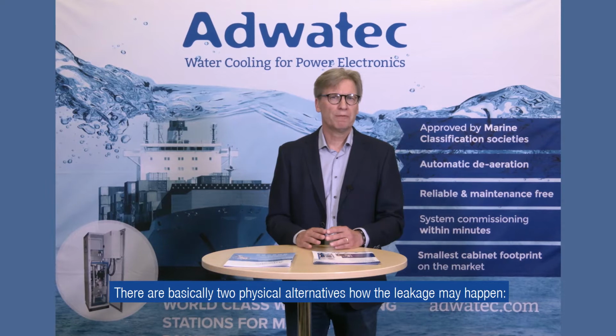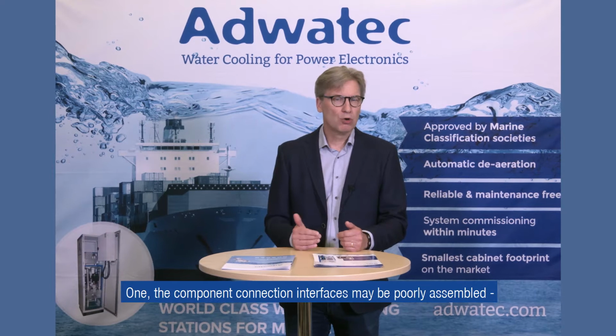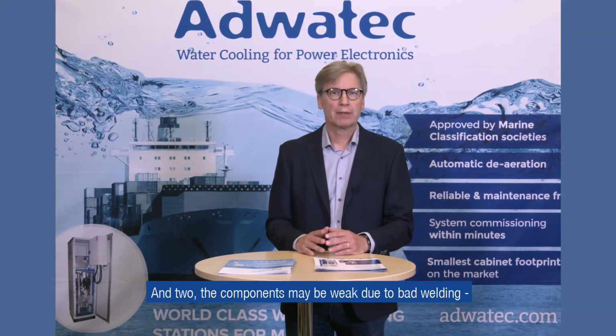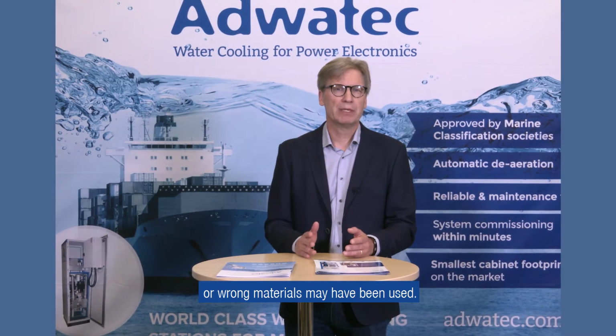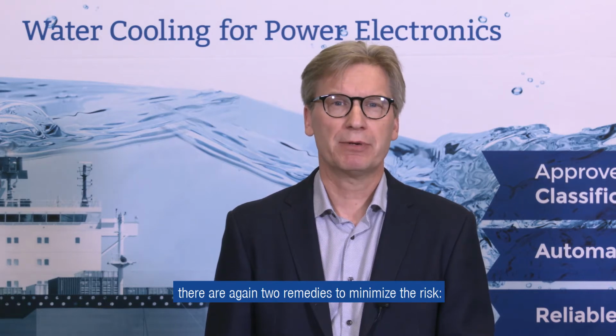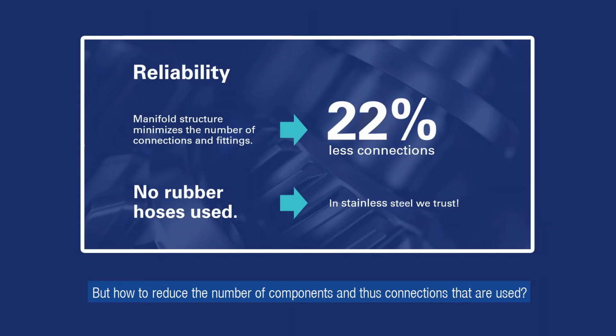There are basically two physical alternatives how the leakage may happen. One, the component connection interfaces may be poorly assembled or may have weak elements like sealing. And two, the components may be weak due to bad welding or wrong materials may have been used. When it comes to component connection interfaces, there are again two remedies to minimize the risk. First, fewer connections means less risk. But how to reduce the number of components and thus connections that are used?